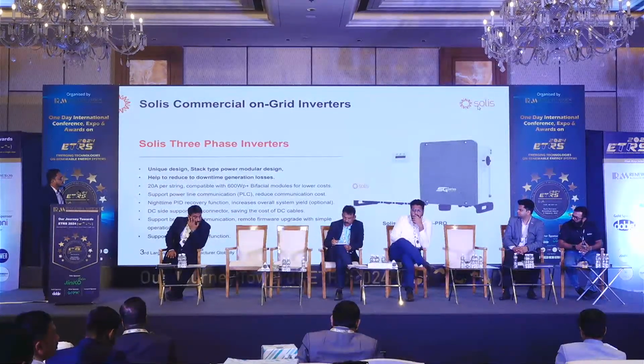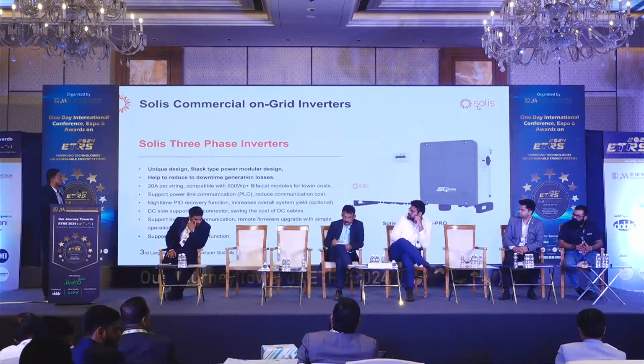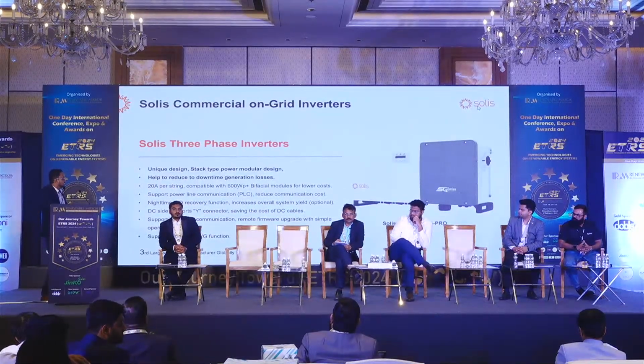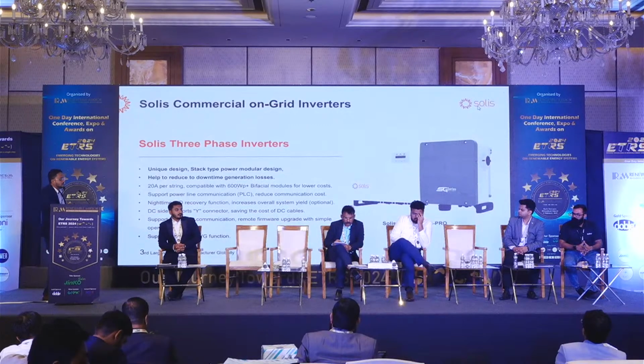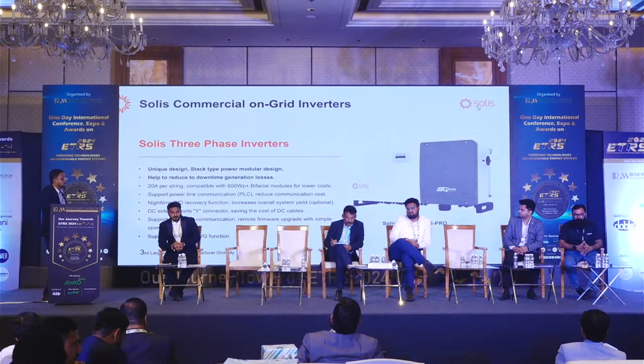This model comes with 20 amps string current and 40 amps MPPT current, and is again compatible with 600 watt peak plus bifacial modules. These inverters come with a power line communication function to reduce communication cost, and we provide a nighttime PID recovery function integrated in all inverters. This again reduces panel degradation. And if the customer wants to reduce DC side cable costs, they can use Y connectors at the panel end, and our inverter is compatible with that. We also give nighttime reactive power compensation, or nighttime SVG functions. This also comes built into this model.